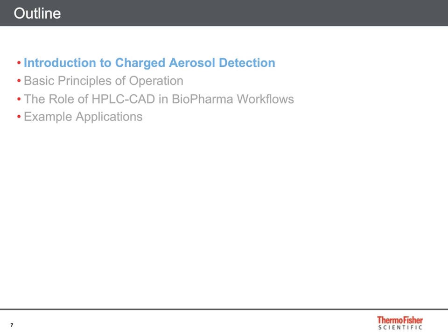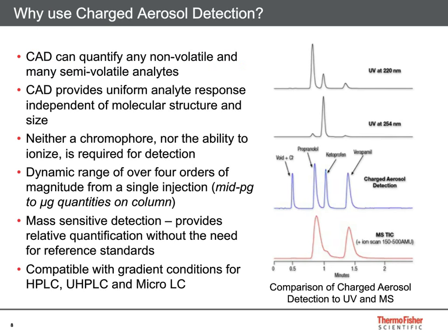We start by asking the question: why use charged aerosol detection at all? After all, HPLC with UV-Vis detection is simple, sensitive, and robust. It has served as the workhorse for pharma and biopharma applications for many years. But no single HPLC detector is ideal. All detectors respond more strongly to some analytes than others. Sometimes one wants a selective detector, such as a fluorescence or electrochemical detector; at other times, one may want a less selective, more universal detector. Charged aerosol detection is often the best choice in the latter case.